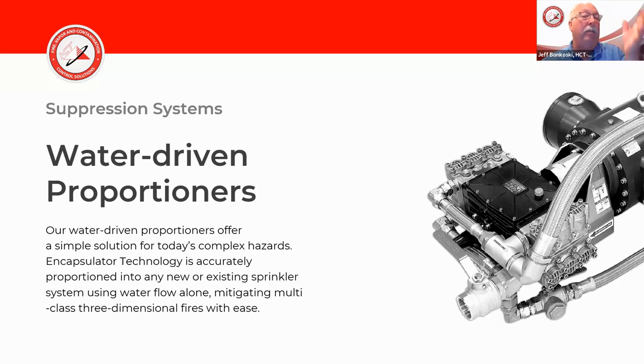So again, we start looking at 1 sprinkler head or 5 sprinkler heads. No matter how many are opening up, as long as it stays within that 250 to 1,250 or whatever the range might be for that particular water-driven proportioner, you're going to get that 3% or the 1% or whatever percentage you're looking for. You're going to get it throughout that whole flow range.